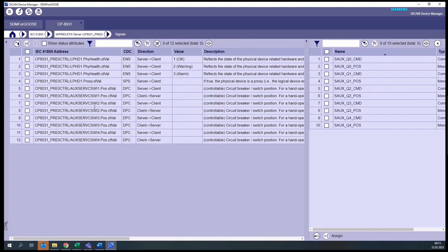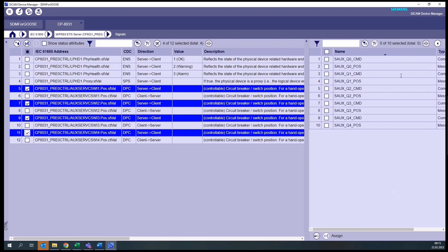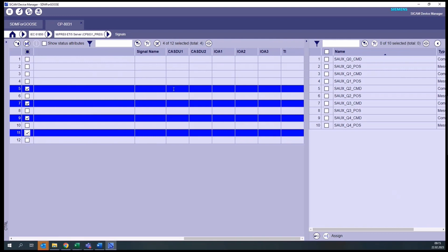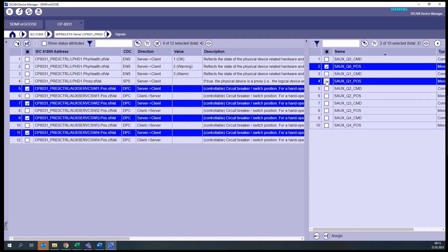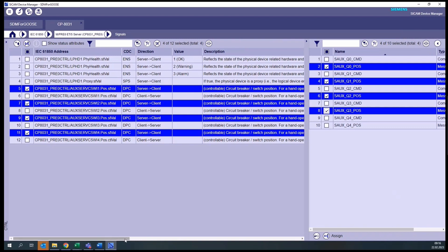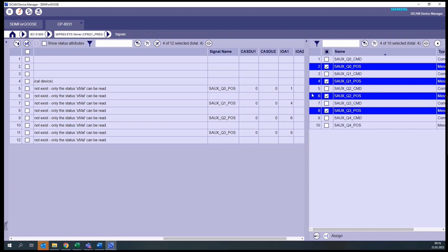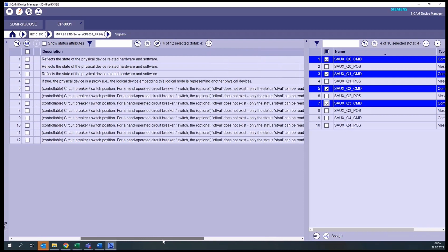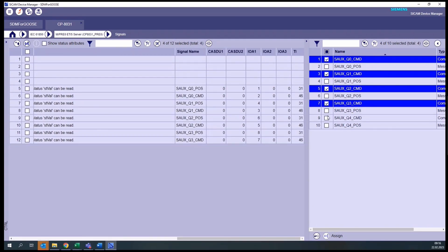You can see on the left the elements selected when we created the data model. We are first interested in the elements indicating the position of these switching devices. To the right, we can see there is a possibility to assign signals to each element. We want to map the positions here, so we mark all four. At the bottom, you can click the button to assign signals to IEC 61850 addresses. And we can do the same with the commands.